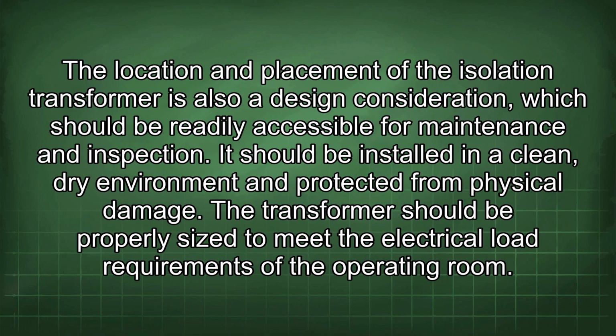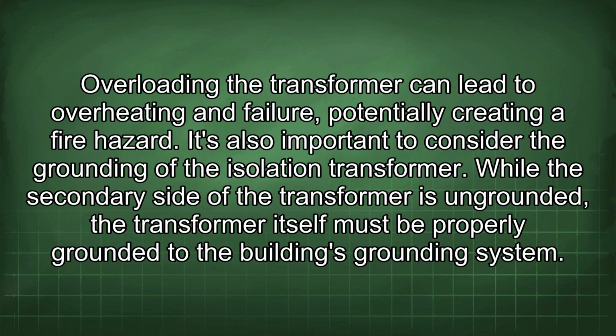The location and placement of the isolation transformer is also a design consideration, which should be readily accessible for maintenance and inspection. It should be installed in a clean, dry environment and protected from physical damage. The transformer should be properly sized to meet the electrical load requirements of the operating room. Overloading the transformer can lead to overheating and failure, potentially creating a fire hazard.